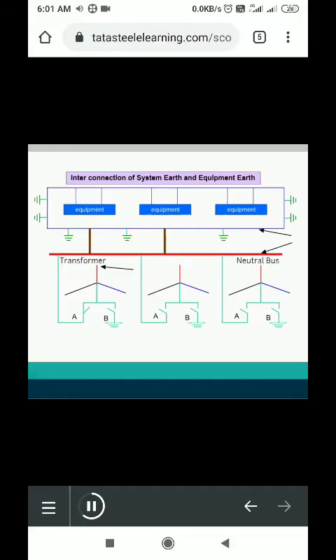Oh, then? Therefore, before putting off switch B to disconnect the power, we will put on switch A first and then put off switch B. Doing this will cause the neutral of the transformer to connect with the mass of earth through the equipment bus bar. This will allow the power to be disconnected to pit B without disturbing power to the installation and work can be carried out. This is all about the connection between system earth and equipment earth.